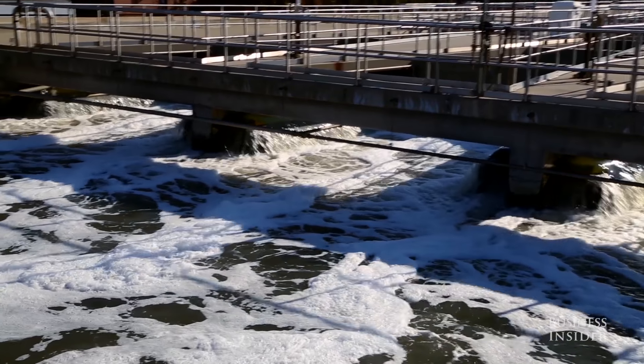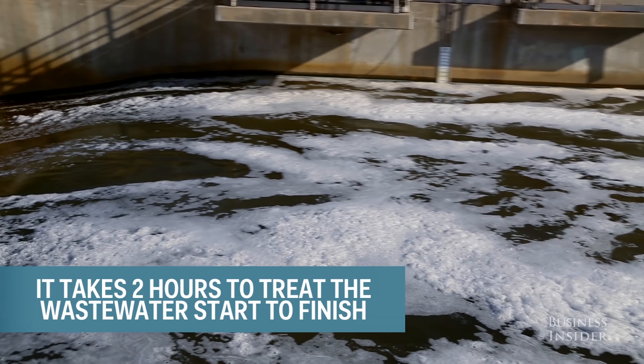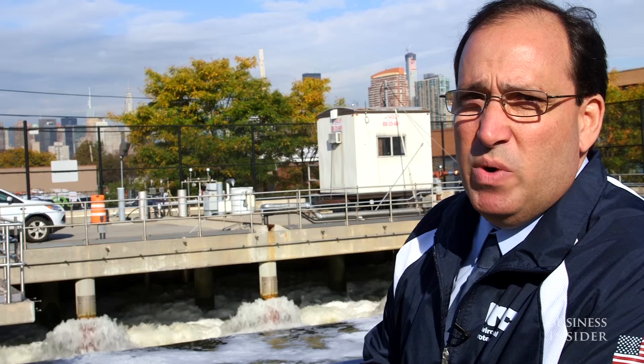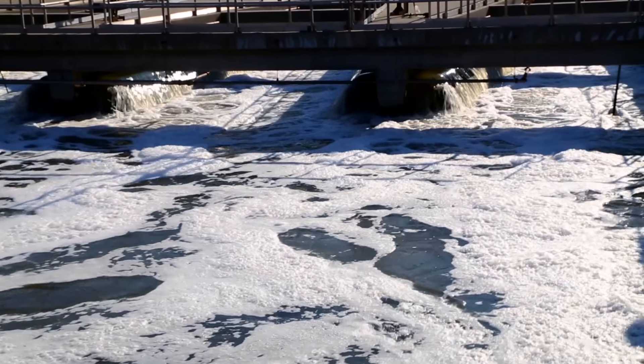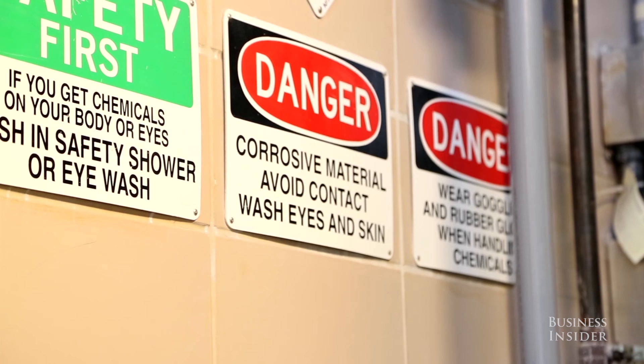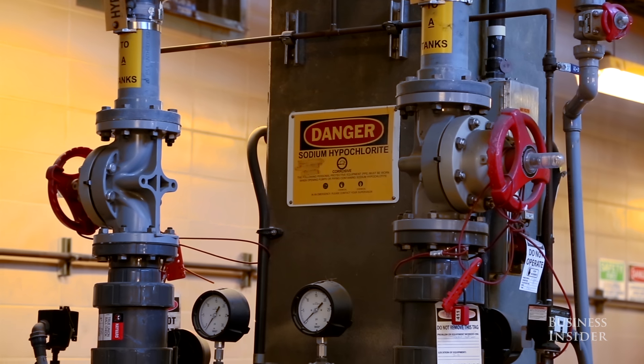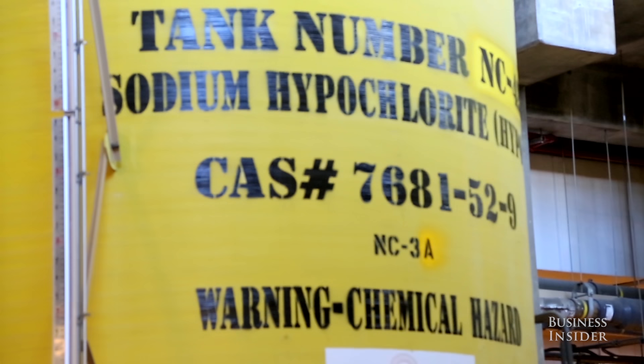This is the last step in the process. We've added bleach to the wastewater, and it's leaving the plant at this point and going down to an outfall that releases the treated sewage into the East River. There are federal regulations that require all wastewater treatment plants in the country to remove at least 85% of the organic material that comes into a plant. This plant generally removes between 92 and 95% of the material, so we do better than federal standards.